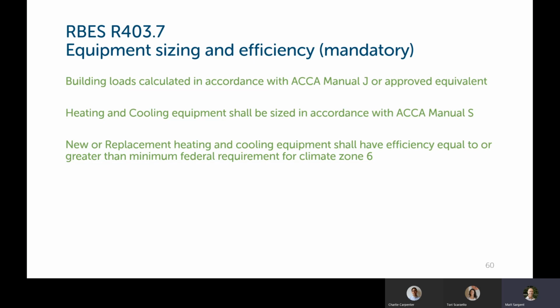RBES R403.7 puts down some guidelines on equipment sizing and efficiency, and this is mandatory. So all building loads have to be calculated using ACCA Manual J or an approved equivalent. Heating and cooling equipment must be sized according to Manual S. The new heating and cooling equipment has to have efficiency greater than or equal to the minimum federal standard for climate zone 6. So the minimum federal standard is not that high. That shouldn't be too hard to hit, but you do have to size it in accordance with Manual S, and your heating loads have to be calculated according to Manual J.